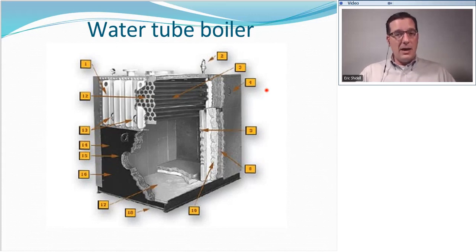Most of the time when you run into one of these boilers, you're going to notice that there is a clear space the same length as the boiler plus a little bit, either in the front of the boiler or behind the boiler. At least they're supposed to be. And that is so that these tubes can be literally pulled out and cut out, and then new tubes slid in place and welded in or pressed in, depending on the style of the boiler. So they can be repaired versus being replaced. As a result, you're going to find some very old-time water tube boilers existing out there in the field. And I've even seen some before with this massive sea of burners underneath them.